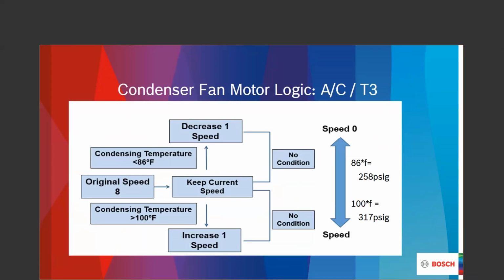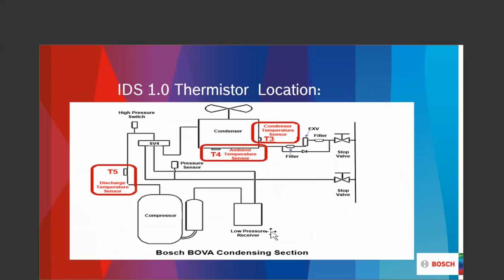So it would be either 86 is 258 PSIG, or 100 Fahrenheit is 317 PSIG. So those represent what's going on with that T3 sensor right there. So this is your logic and location of the sensors. T5 is that discharge sensor. T4 is your ambient temperature.